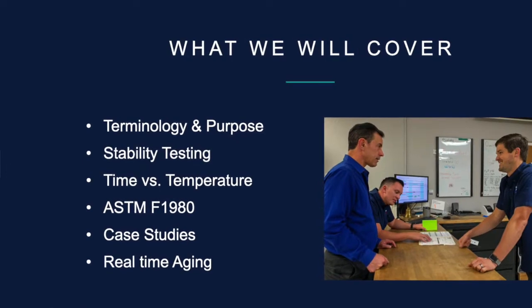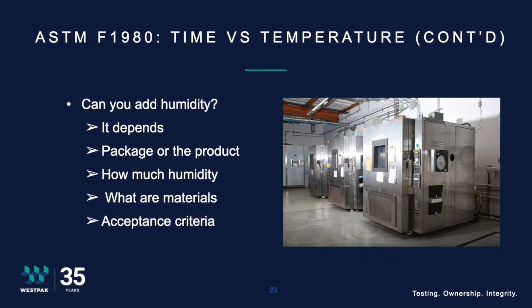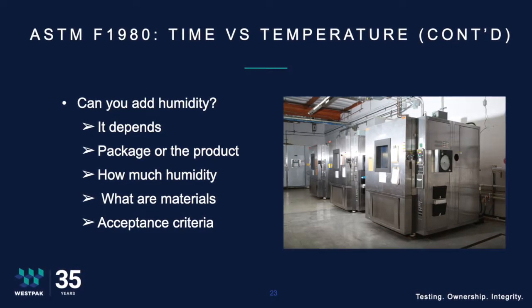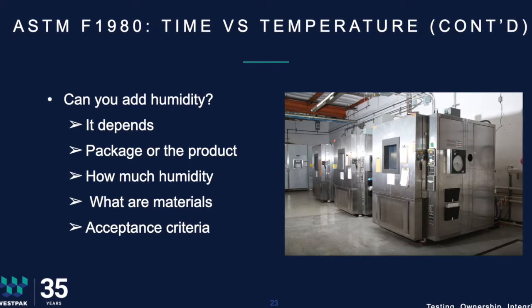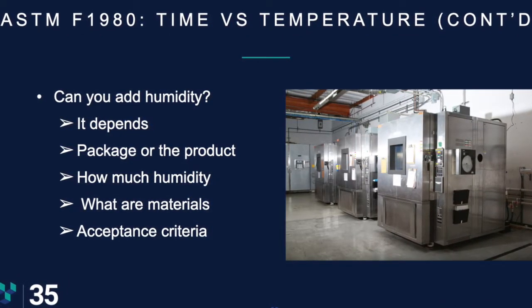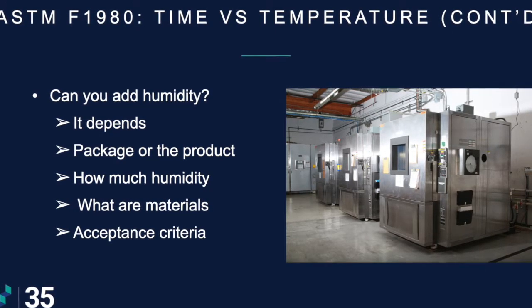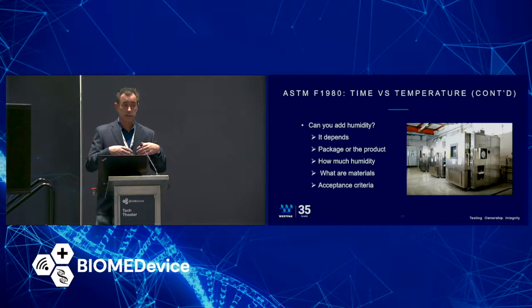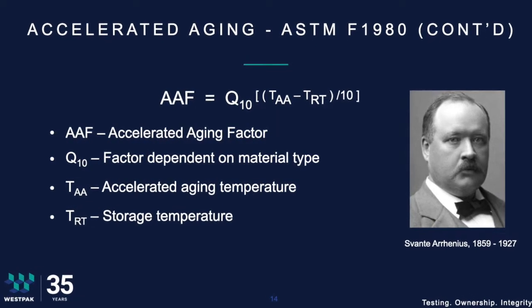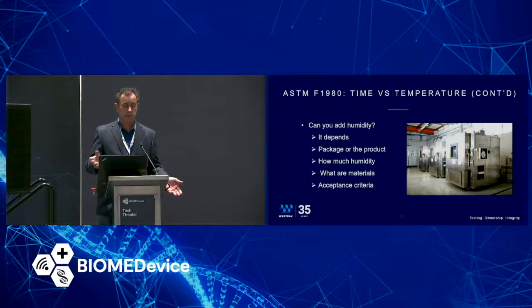We're going to talk about the principles of accelerated aging, specifically the standard in reference to humidity. This is a question we get a lot: 'I want to put humidity into my aging.' The answer is: it depends — are you looking at the package or the product? Packaging materials aren't necessarily sensitive to humidity. And if we look at the Arrhenius equation, he doesn't mention anything about humidity — not percent humidity, relative humidity, moisture ratios, or anything like that. So we don't really need to add humidity into the equation.